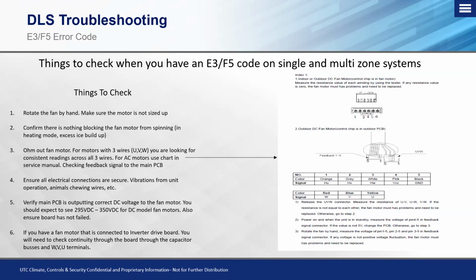Yeah, there could be a multitude of issues. Could be wiring connections, could be a board related issue, could be something that's caught up in the fan motor, or it just could be a faulty fan motor itself. Okay, but we want to make sure that there's of course nothing obvious. So we want to rotate that fan motor by hand, make sure it's not seized up. We want to confirm that there's nothing blocking or in the way of that outdoor fan motor as it's trying to start up and run.